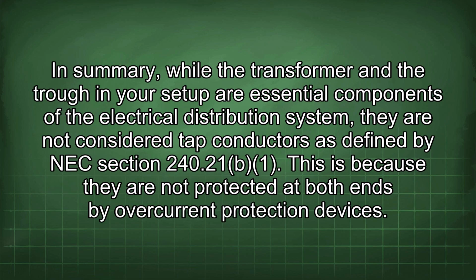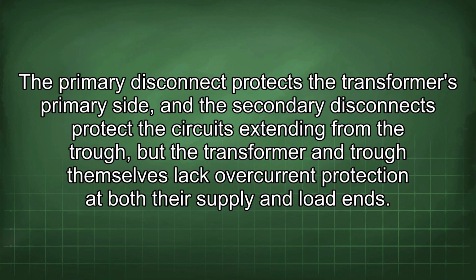In summary, while the transformer and the trough in your setup are essential components of the electrical distribution system, they are not considered tap conductors as defined by NEC section 240.21. This is because they are not protected at both ends by overcurrent protection devices. The primary disconnect protects the transformer's primary side, and the secondary disconnects protect the circuits extending from the trough, but the transformer and trough themselves lack overcurrent protection at both their supply and load ends.